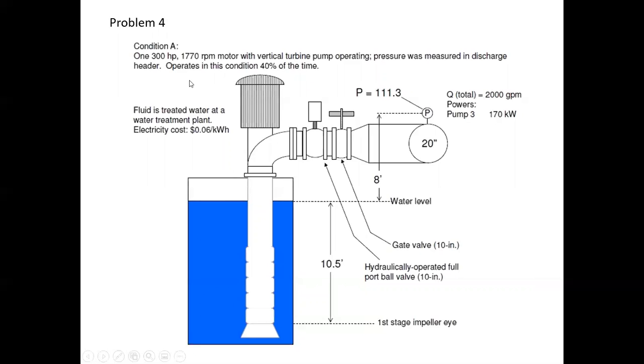So that's the elevation of fluid above it that we want to take into consideration. Okay, so condition A, we have one 300 horsepower, 1770 RPM motor with a vertical turbine pump operating. Pressure was measured in the discharge header, and it operates in this condition 40% of the time. The fluid is treated water in a water treatment plant, 6 cent power. So the impellers push up through here. And what do we got? We've got a hydraulically operated full port ball valve, 10 inches. We got a 10-inch gate valve. And then we go from 10 to a 20-inch pipe. And there we go.